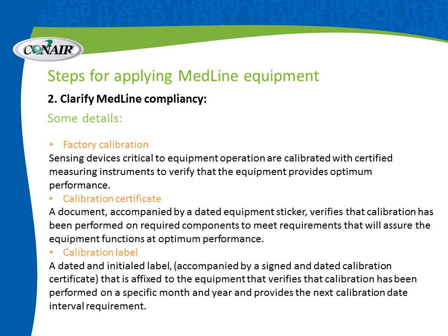We say that it will work the way it says it will work, and we provide a calibration certificate saying exactly that: when it was calibrated, who did it, and when it will need calibration again. We also provide that same type of identification with a label that actually goes right on the equipment. And so this is really covering all the bases on calibration.